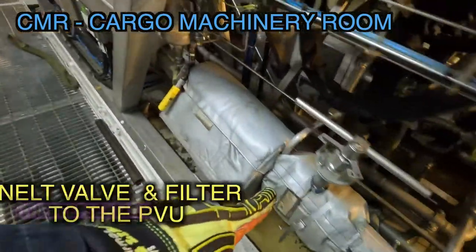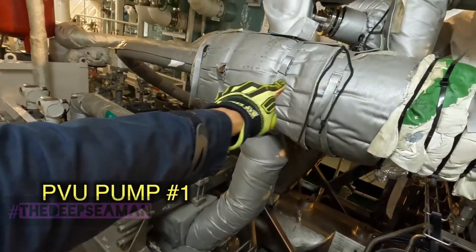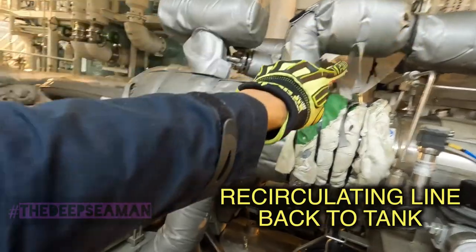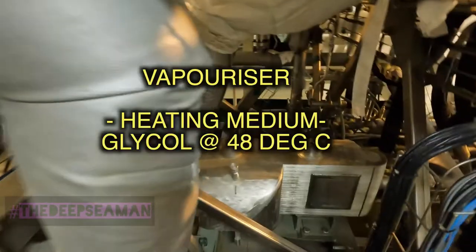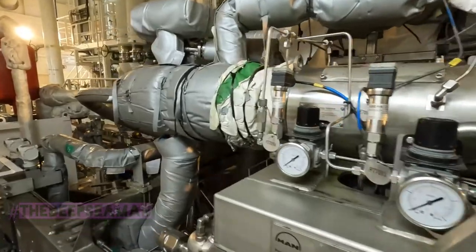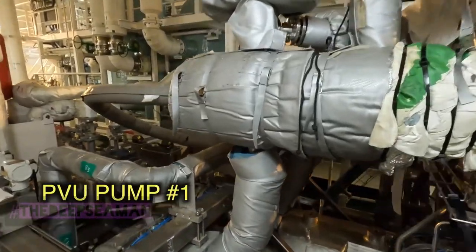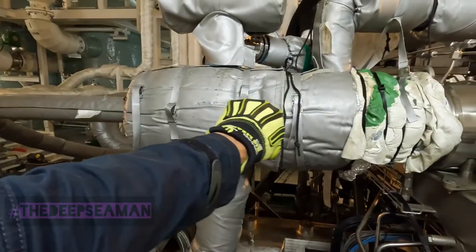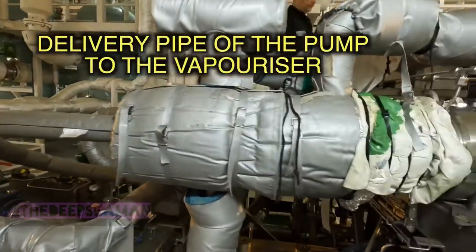Let's head to the CMR - this is the skid where the PVU cryogenic pumps are mounted. You can see the inlet valve to the cryogenic pumps, the first cryogenic pump, and its reciprocating motion. That is the recirculation line going back to the tank. This is the delivery line of pump number one going to the common manifold and then into the vaporizer, which is heated by glycol.